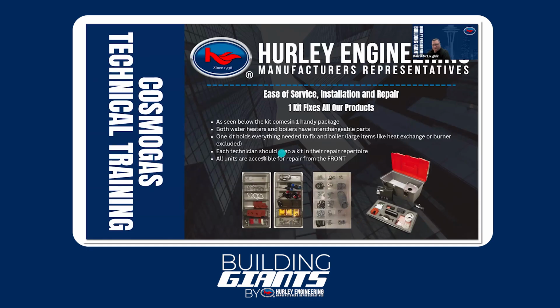Another thing they do, and I'm going to take the time to talk about this real quick, because service is such a key aspect of what they're trying to provide, and they make them easily serviceable. They've got this parts kit. So if you ever need to service it, the parts kit is really what they would prefer you to have. If you buy this one parts kit, it's got every part that you could need for about 95% of the issues. So when I say that, that means every gasket you need, igniters, flame rods, gas valves, fuses, anything down to a new burner control, a blower motor. All those things are already included.